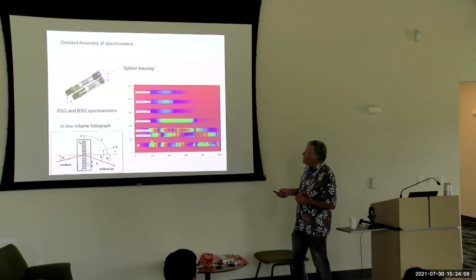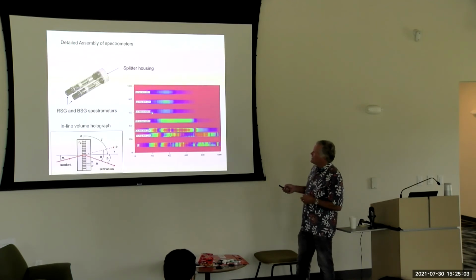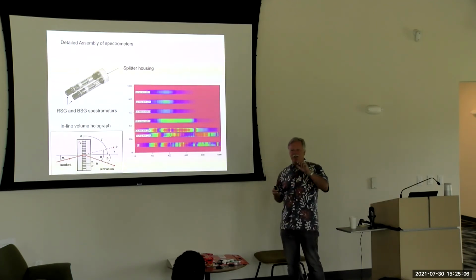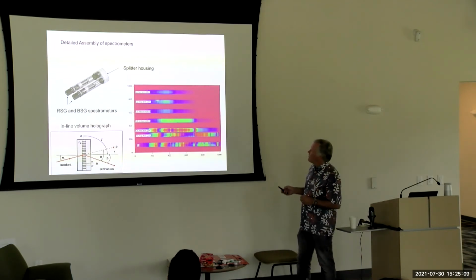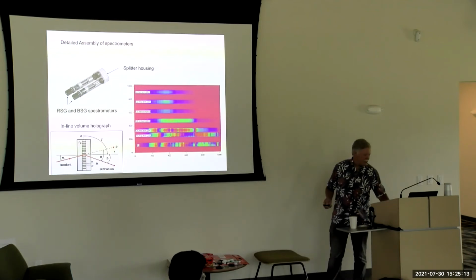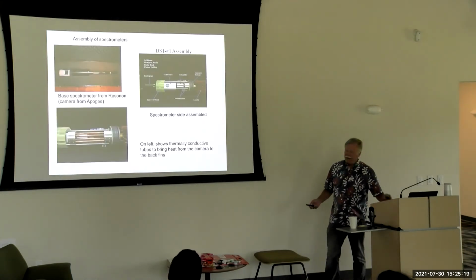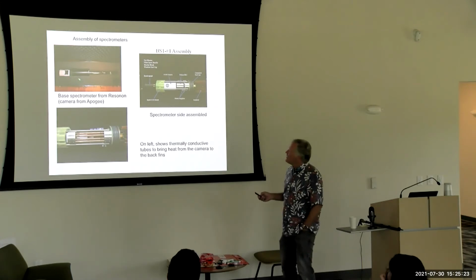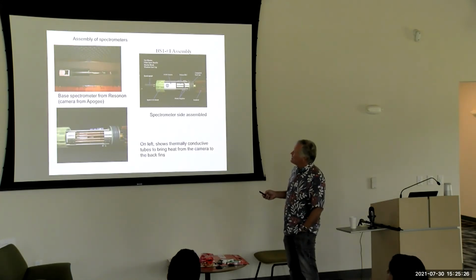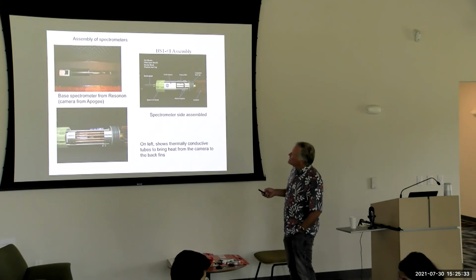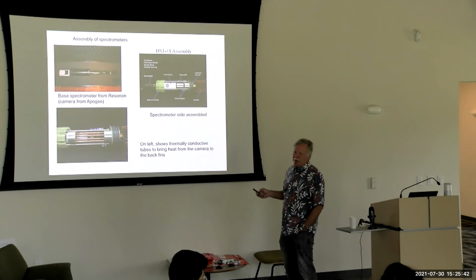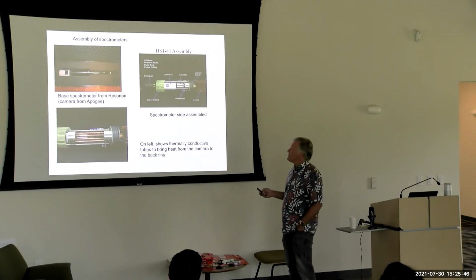Basically, we're probably not going to do them all at once. We're probably going to take ES and the LUs at the same time, so that you can keep those normalized together. But anyway, we have the ability to do multiple measurements. We can make 14 different tracks of measurements on the detector with the system. Here's a picture. So I'm going to show you the assembly. So here's the Resonon. The base spectrometer was built by Resonon with the camera from Apogee. Back here is the camera. In here is that inline volume holographic grating. It's all black. Out here is 14 fibers, one that goes to each of the possible channels we can have. So this is the thing we start with.